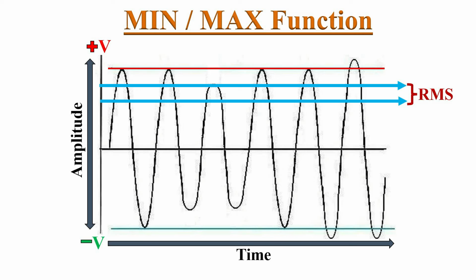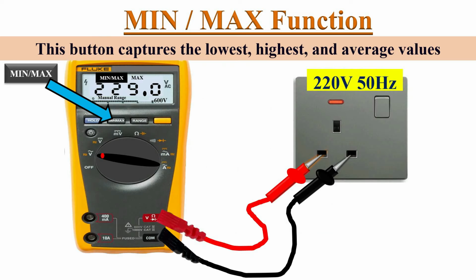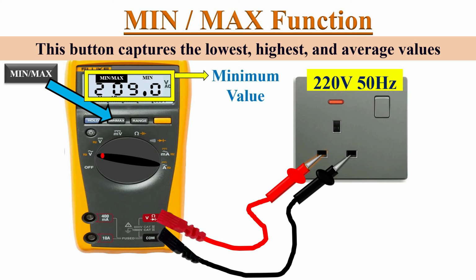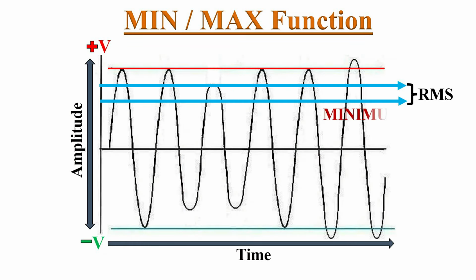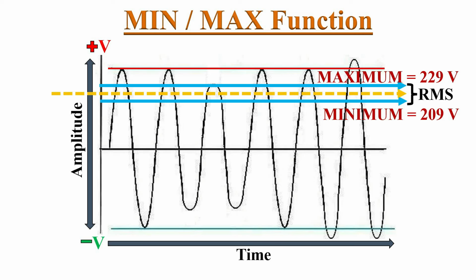Suppose the RMS value is fluctuating between these two values, we can consider the lower reading as the minimum value and the upper reading as the maximum value. This 229 volts is the maximum value of this measurement. Just press this min-max button again. Now the meter enters into minimum value mode and displays the minimum value of the measurement. Here our minimum measurement is 209 volts and maximum measurement is 229 volts. If we calculate the average value, it must be 219 volts.